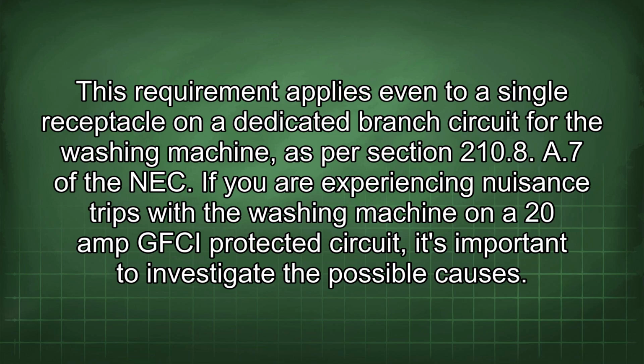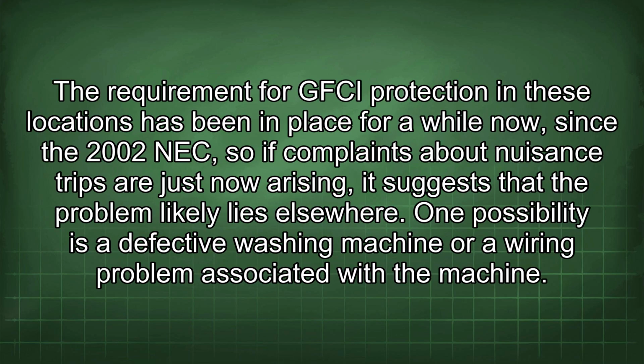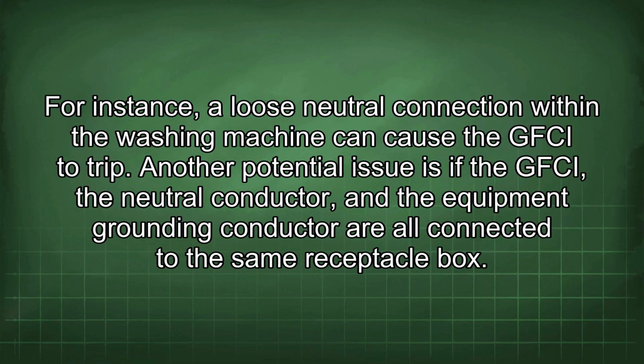If you are experiencing nuisance trips with the washing machine on a 20 amp GFCI protected circuit, it's important to investigate the possible causes. The requirement for GFCI protection in these locations has been in place since the 2002 NEC, so if complaints about nuisance trips are just now arising, it suggests that the problem likely lies elsewhere. One possibility is a defective washing machine or a wiring problem associated with the machine. For instance, a loose neutral connection within the washing machine can cause the GFCI to trip.